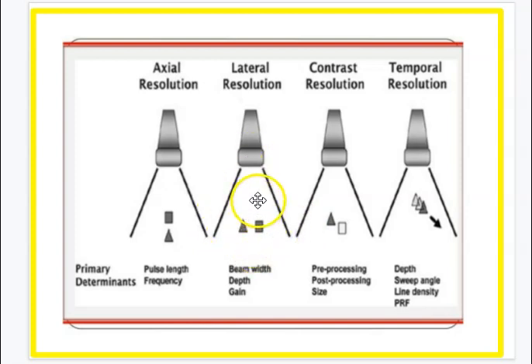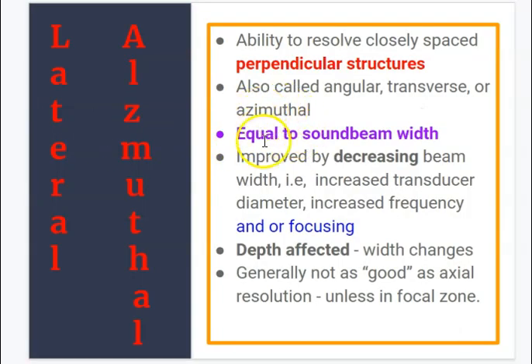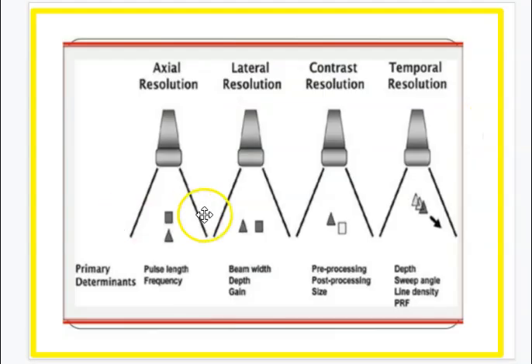The reason this isn't as good in many situations is because, first off, here you're going straight down, and as you spread out the beam, you make it wider. It's got to sweep through this area, so this resolution is going to be a little bit wider, and you're not going to be able to see things quite as well. It's equal to the sound beam width, right? So if the sound beam width is really wide in that area, it's going to be difficult to see these two objects really clearly.